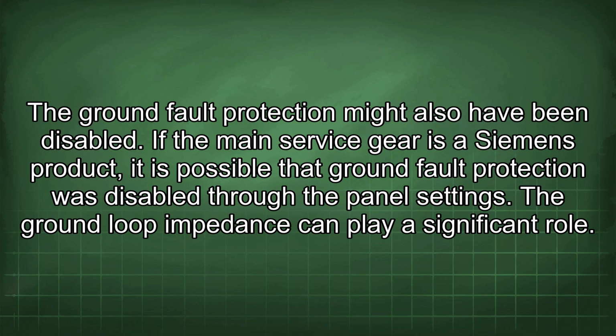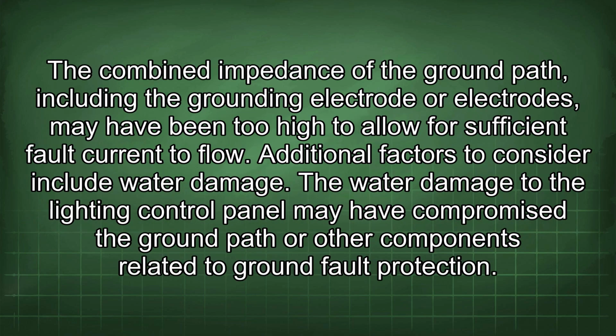If the main service gear is a Siemens product, it is possible that ground fault protection was disabled through the panel settings. The ground loop impedance can play a significant role. The combined impedance of the ground path, including the grounding electrode or electrodes, may have been too high to allow for sufficient fault current to flow.